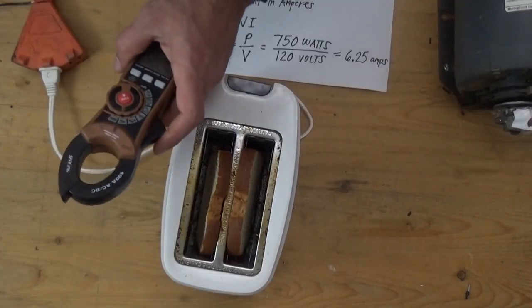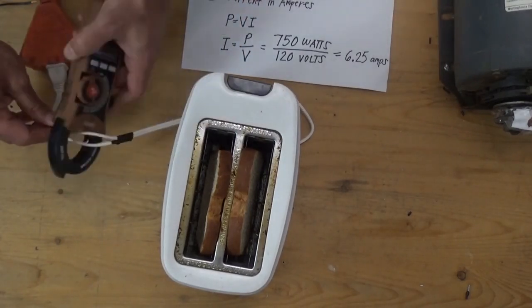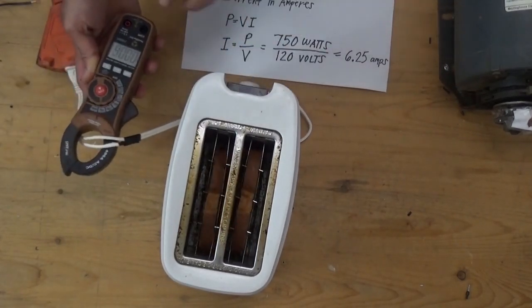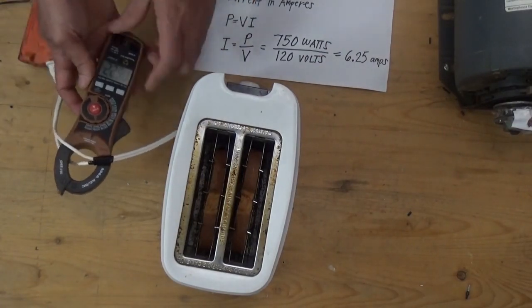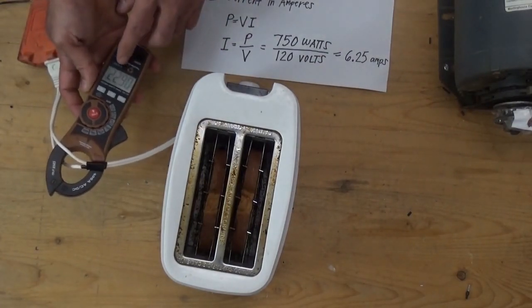When using a clamp ammeter, do not clamp it on two wires. See here, we have zero current. Let's clamp it on one wire. See, our current is 6.22 amperes.